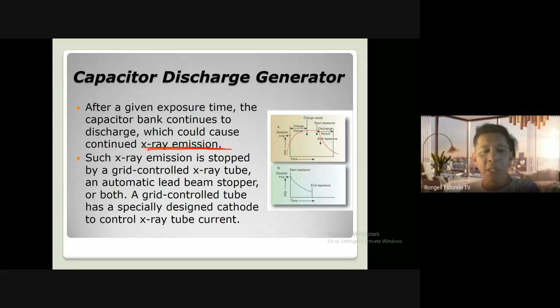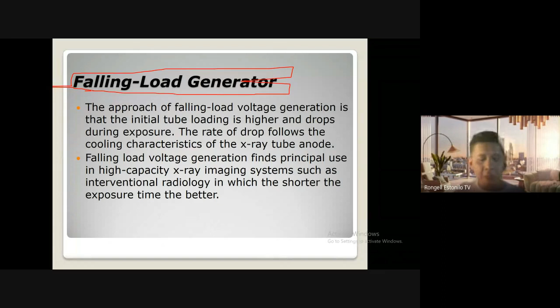Next, we have, of course, the falling load generator, which na-discuss naman natin sa operating console. So the approach of falling load voltage generation is that the initial tube loading is higher and drops during exposure. So the rate of drop follows the cooling characteristics of the X-ray tube anode. And then falling load voltage generation finds principal use in high-capacity X-ray imaging systems such as interventional radiology, in which the shorter the exposure time, the better. Again, the shorter the exposure time, the better. Kasi, di ba, falling load, nag-start siya at higher voltage or current. Kaya falling. So, the rate of drop follows the cooling characteristic of the tube anode.